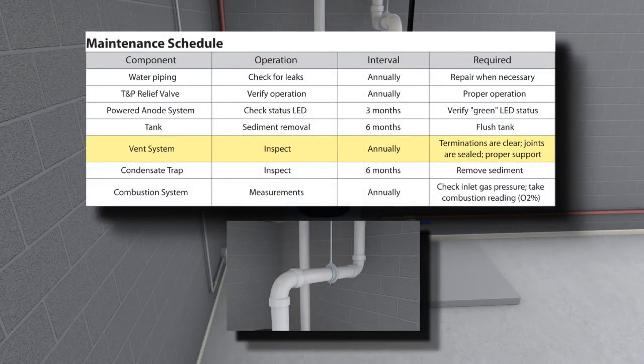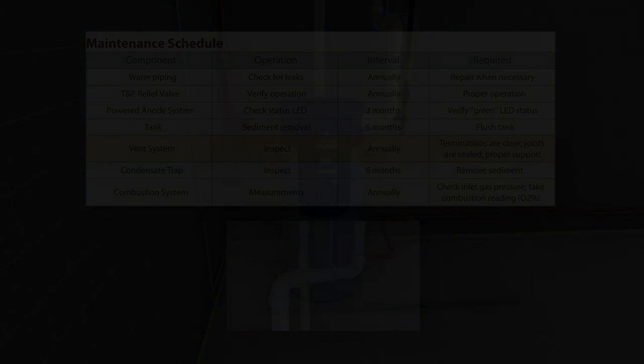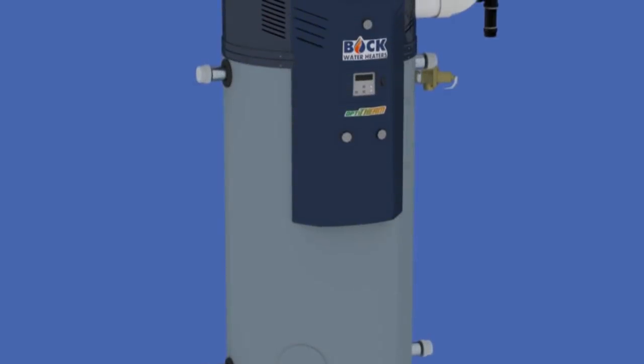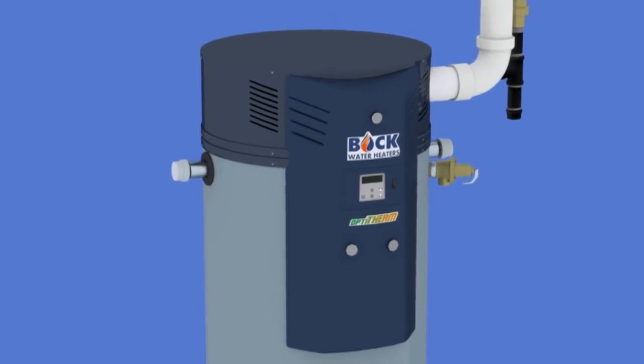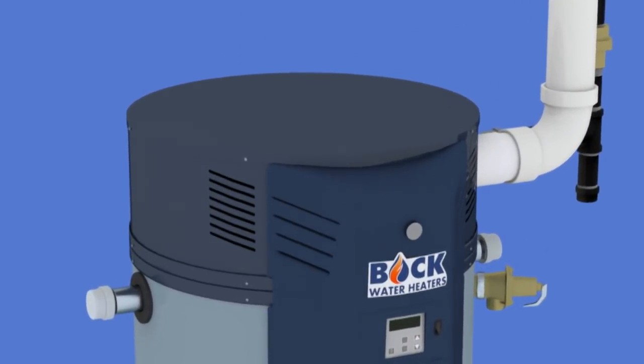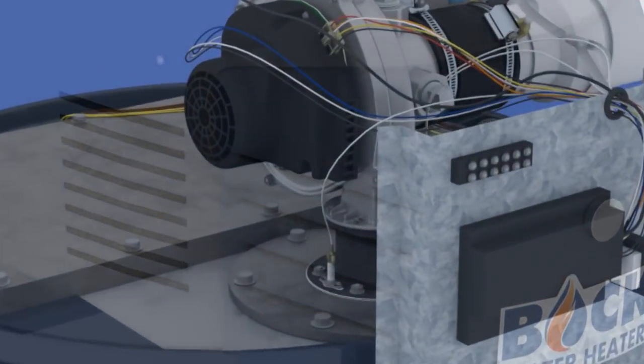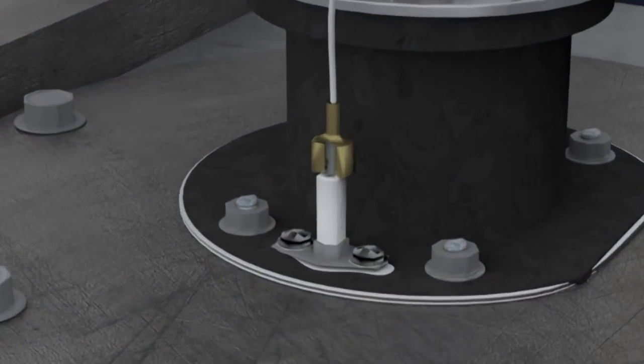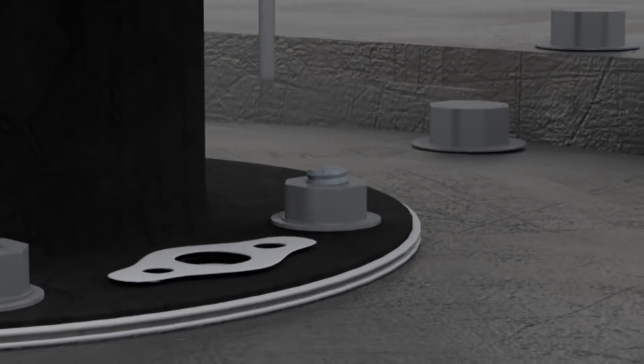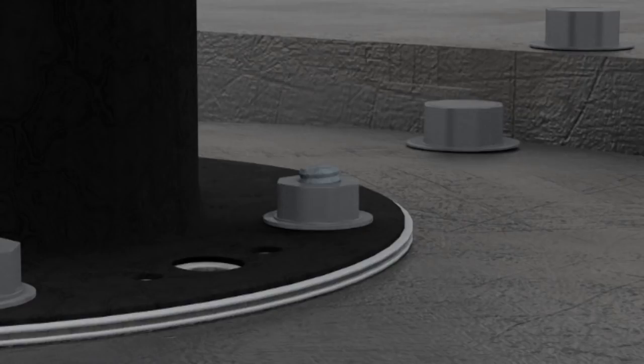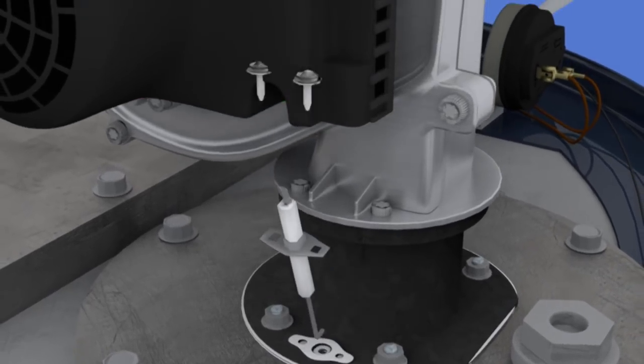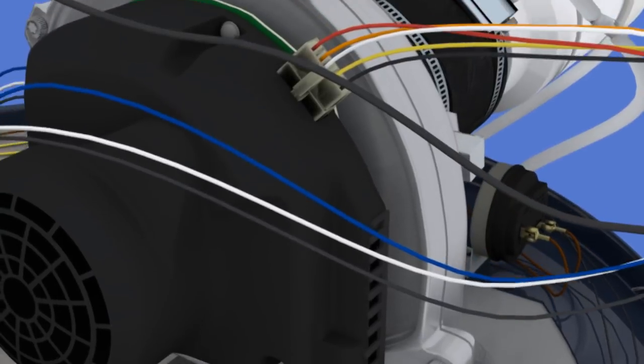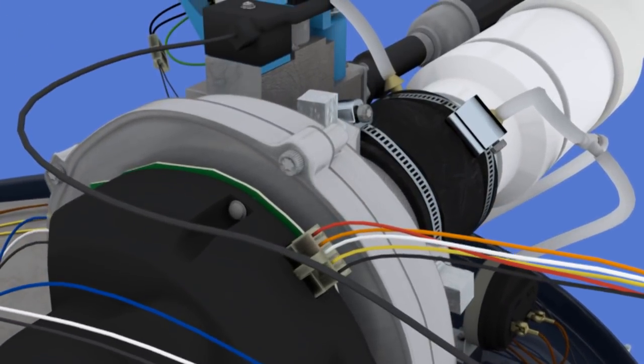Inspect venting system. The vent and combustion air intake system should be checked at least once per year for damage and blockage. To inspect the burner, the intake vent connection, blower, and gas valve must be removed. Turn off gas and disconnect power. Disconnect the igniter and flame rod wiring. Remove the igniter, gasket, and set aside. Remove the flame rod, gasket, and set aside.